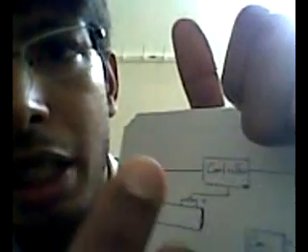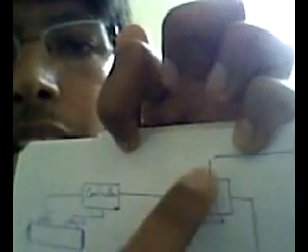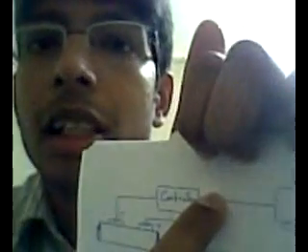The controller would calculate the value by which your valve has to be controlled. So from the controller it is transmitted back to your valve and it would regulate it. Now somebody has to give it a set value, right? That set value to the controller would be given from the operating station over here. Can you see this desktop that I've drawn? From here somebody would indicate to the controller that this is the particular set point value I need.